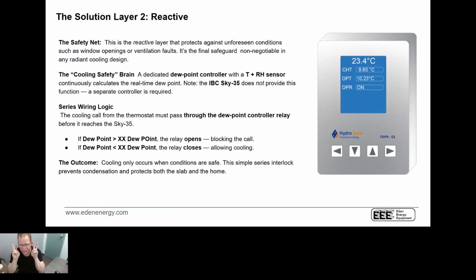So this is the reactive. This is, okay, we put in an Aprilaire or a Honeywell dehumidifier. We're going to reduce the humidity in the space. We're going to set the water temperature to the floor at 63 or 66 degrees. We'll get 17 BTUs per square foot. But again, what happens if somebody opens all the windows on the main floor? This is the reactive mandatory response, which is a dew point controller. So what's going to happen is it's just a simple relay contact that if the dew point goes too high, it's going to disable the cooling.